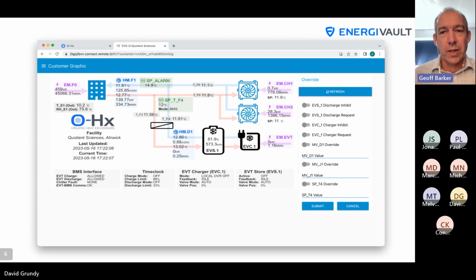So again, using the Quotient example, at the early part of the year when the demand is lower, because obviously the ambient conditions are not as hot, then you might see EnergiVault as the primary chiller more often than not, because it can operate for at least 3 or 4 hours, and therefore it could be operated as a primary chiller between 4 o'clock and 7 o'clock, for example, thereby avoiding the high cost triad charges, distribution charges in the UK. During the summer, it may be set up as the support chiller number 3, so it effectively ensures that the demand is met, and acts as a support chiller. So throughout the year, the BMS can configure it in a different way to deliver the optimum performance and optimum savings. So effectively it connects to a local BMS. A long answer to a short question.